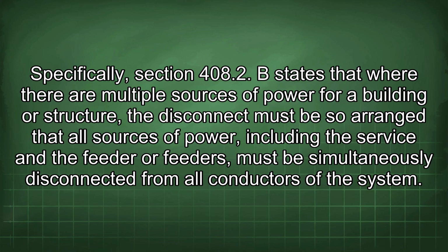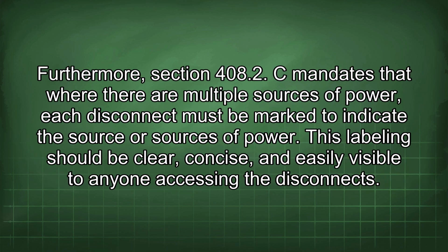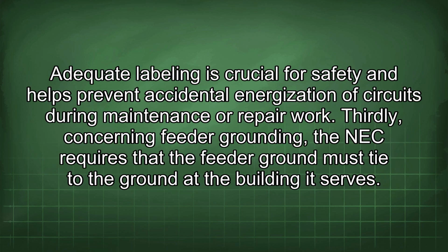conductors of the system. Furthermore, section 408.2(C) mandates that where there are multiple sources of power, each disconnect must be marked to indicate the source or sources of power. This labeling should be clear, concise, and easily visible to anyone accessing the disconnects. Adequate labeling is crucial for safety and helps prevent accidental energization of circuits during maintenance or repair work.